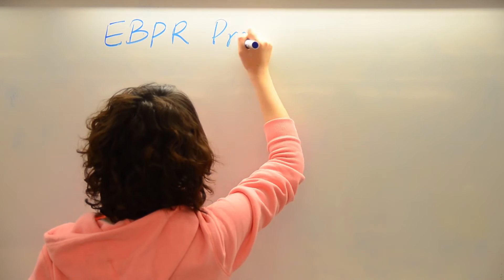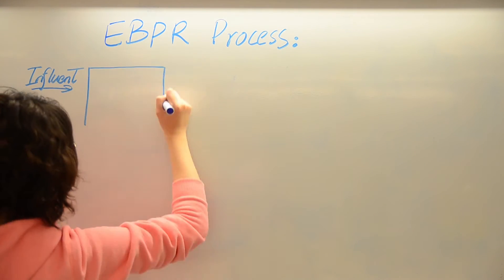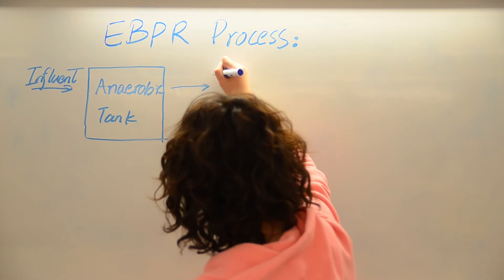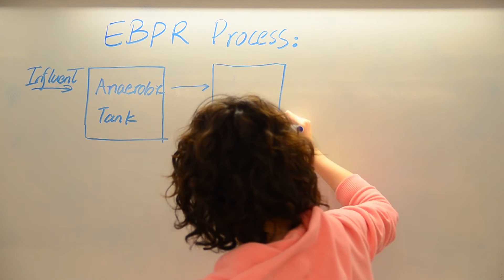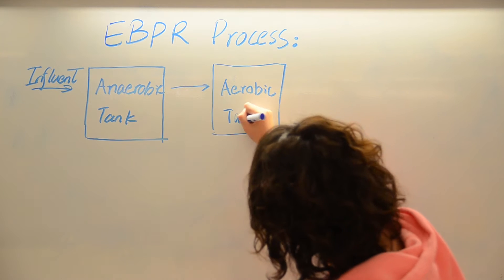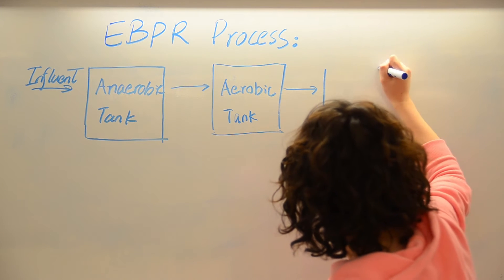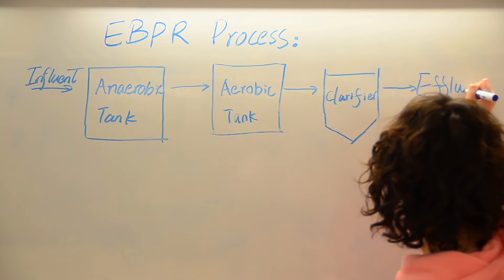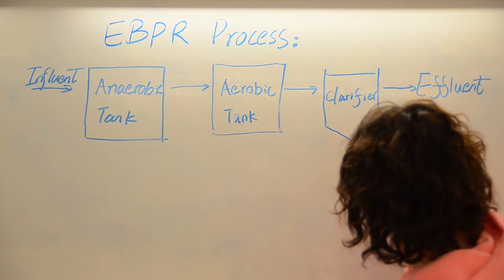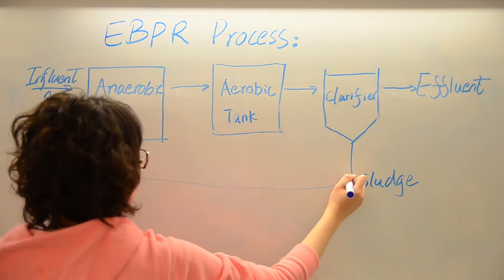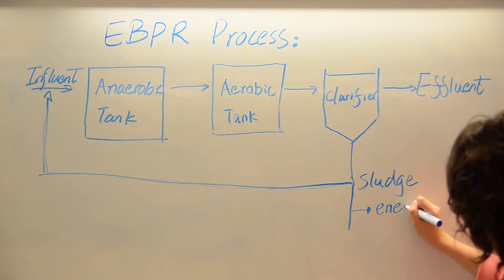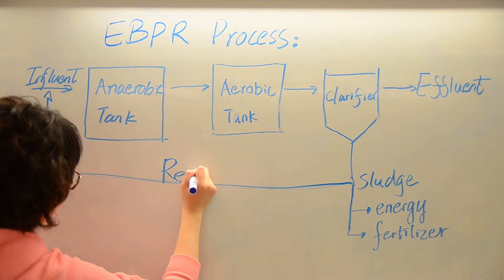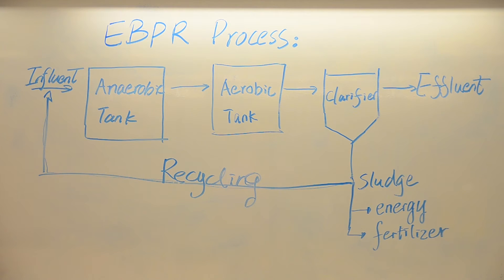There are two main phases in EBPR. First, the bacteria are held in an anaerobic tank, where they store energy and have a competitive advantage over other organisms. Then, the bacteria are transferred to an aerobic tank, where they grow rapidly, uptaking phosphorus. Everything then goes into a clarifier, where the sludge and water are separated. A bit of the activated sludge is recycled to inoculate the influent water, while the rest can be used for energy or as fertilizer. Much of the organic matter, minerals, nitrogen, and phosphorus are stored in the sludge, making for a fertilizer that is rich in nutrients and minerals.